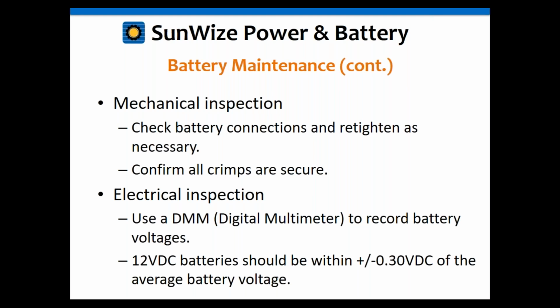Check battery connections and retighten as necessary. Very important. They can loosen up from thermal cycling. That happens quite a bit, so it's important to always check those and retighten them as necessary. Crimps as well. I've seen a lot of crimps fail over the years. The connections can corrode at the termination points. I've seen that a lot. They can fail that way. So you always want to check the crimps, make sure they're still tight and they haven't failed.